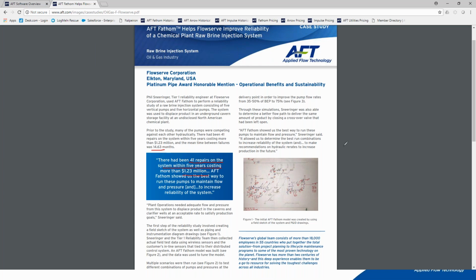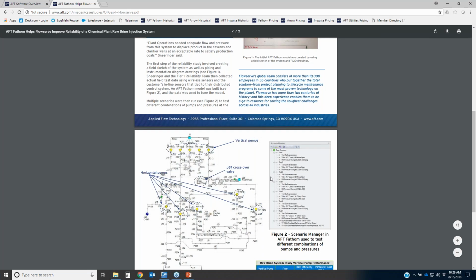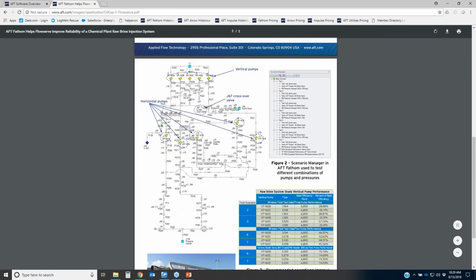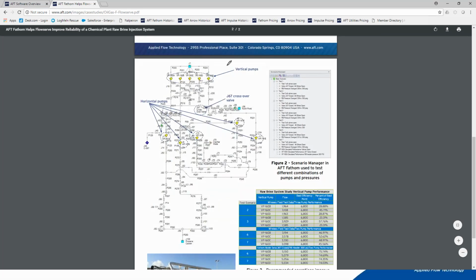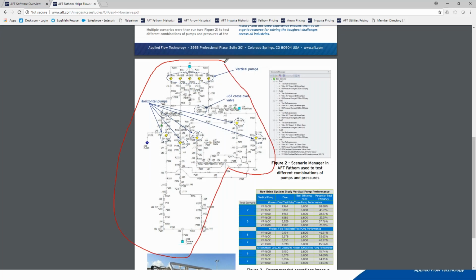So they're constantly having problems in their system, having to go back and make repairs, and just had tons and tons of issues. Well, as Flowserve began to look deeper into what was going on, they built a model of their piping network, and this is what the model looks like right here. And so they had 10 pumps in the system. These were vertical supply pumps, and then they had some horizontal booster pumps elsewhere throughout the system.